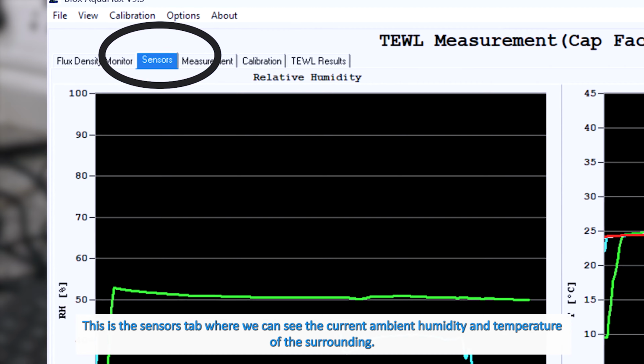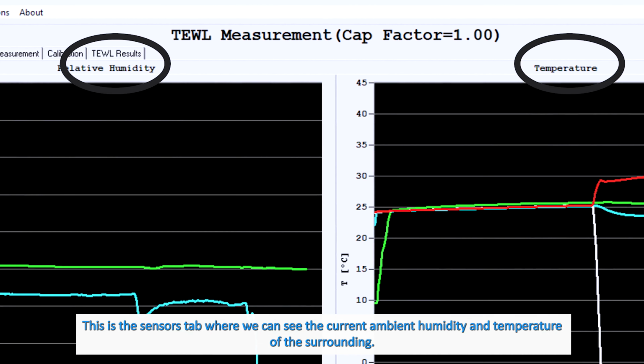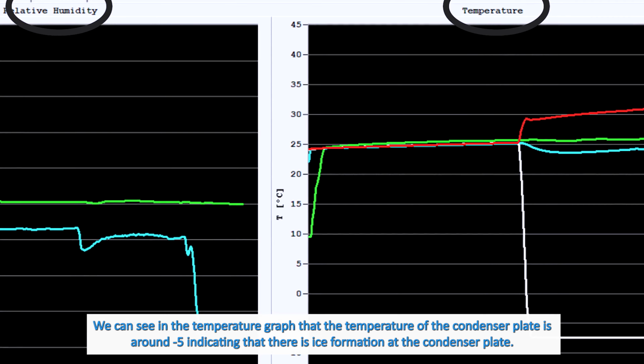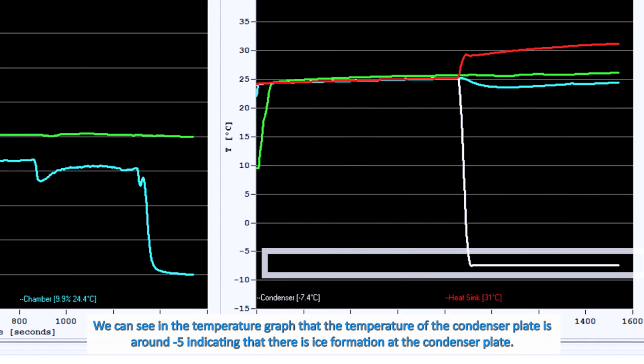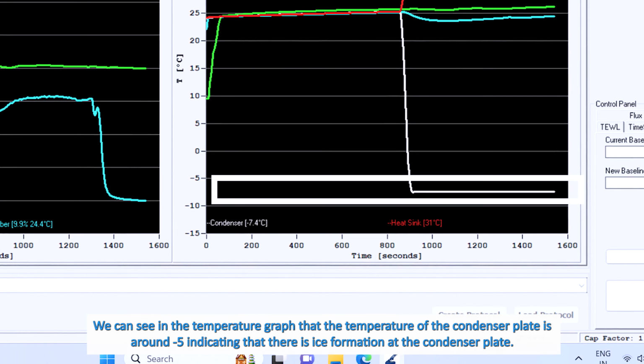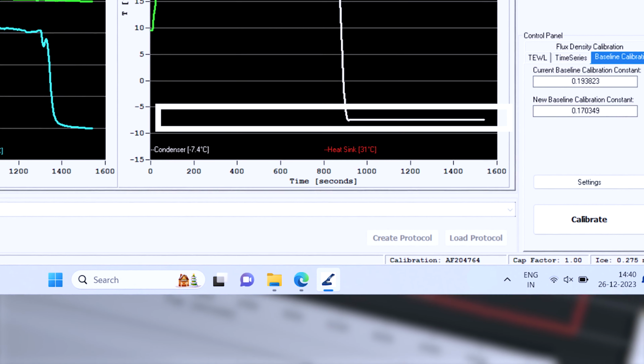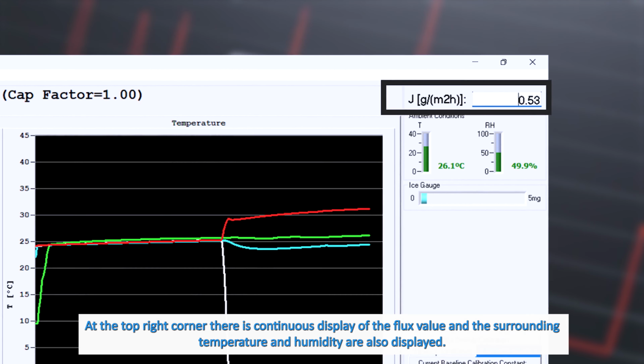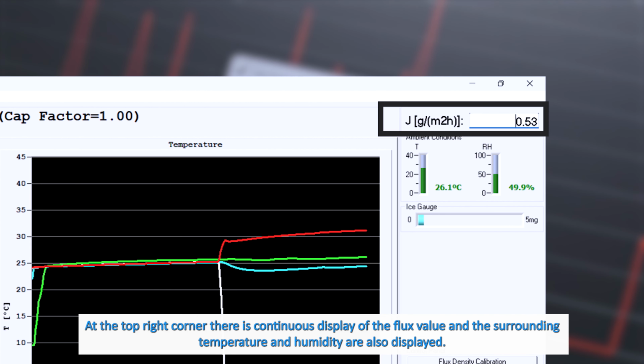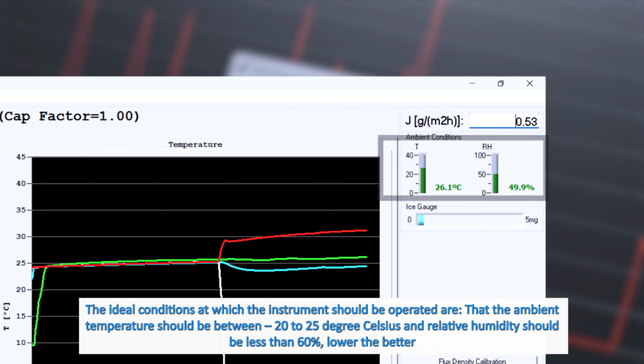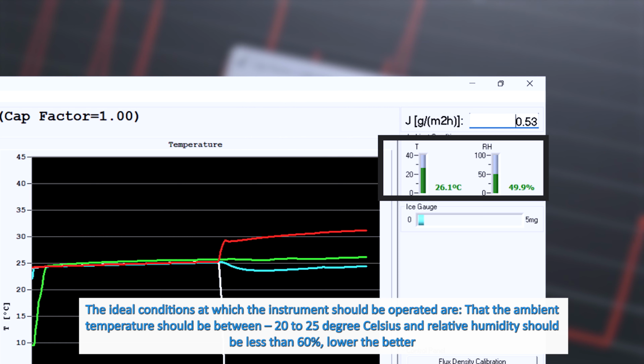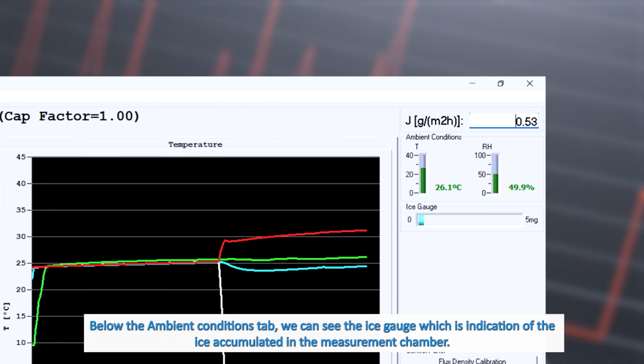This is the Sensors tab where we can see the current ambient humidity and temperature of the surroundings. We can see in the temperature graph that the temperature of the condenser plate is around -5, indicating that there is ice formation at the condenser plate. At the top right corner, there is a continuous display of the flux value, and the surrounding temperature and humidity are also displayed. The ideal conditions at which the instrument should be operated are that the ambient temperature should be between 20 to 25 degrees Celsius and relative humidity should be less than 60%, the lower the better.